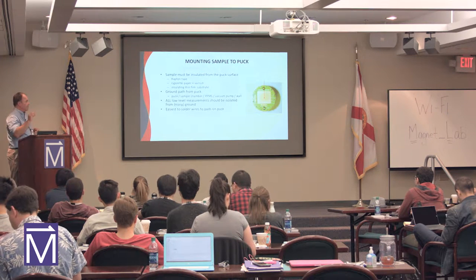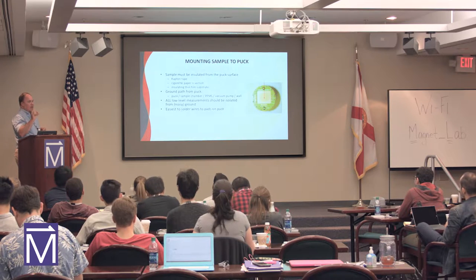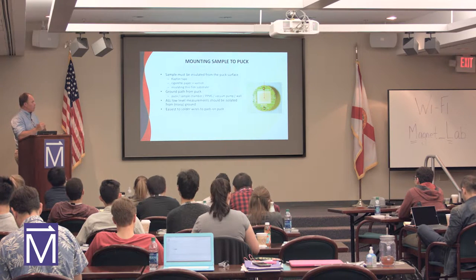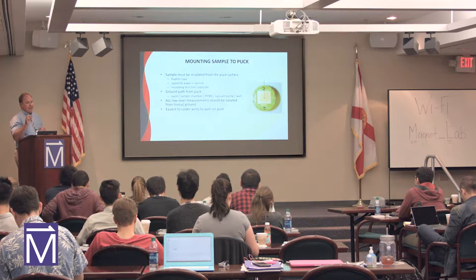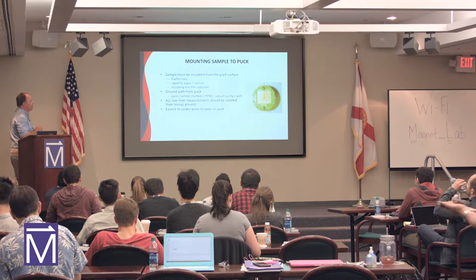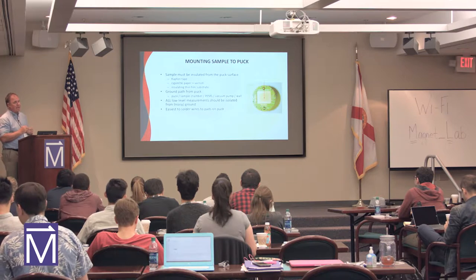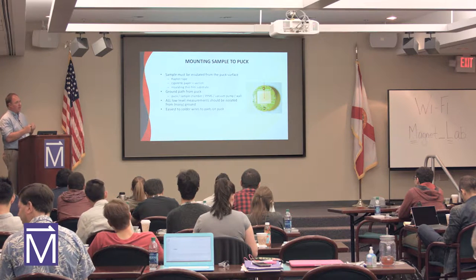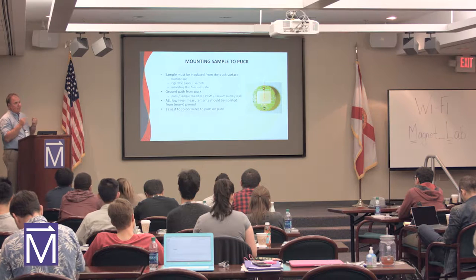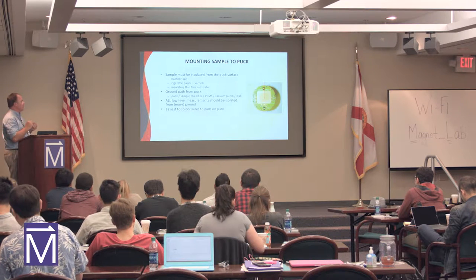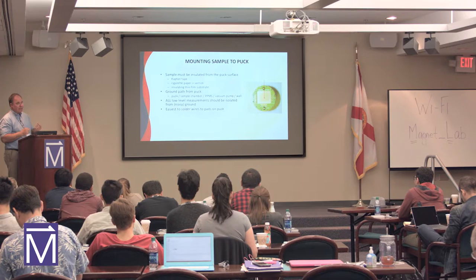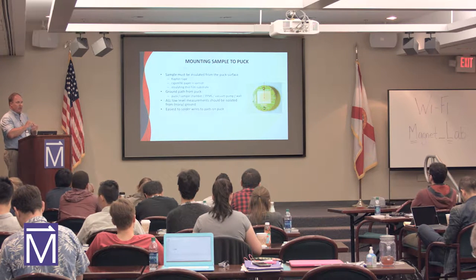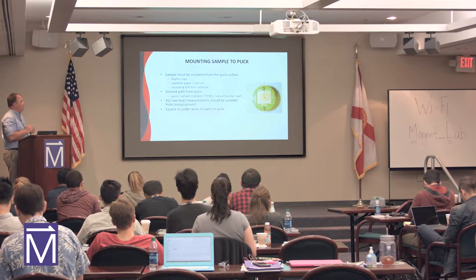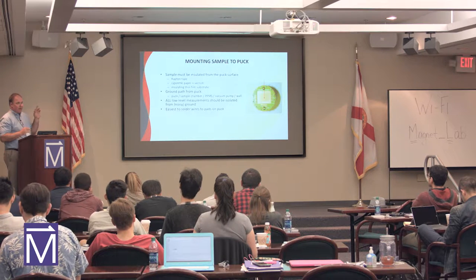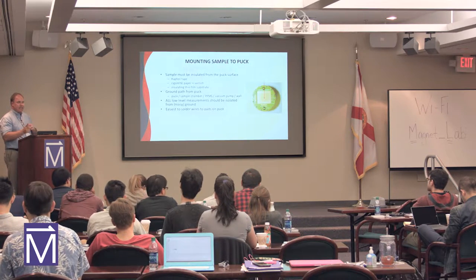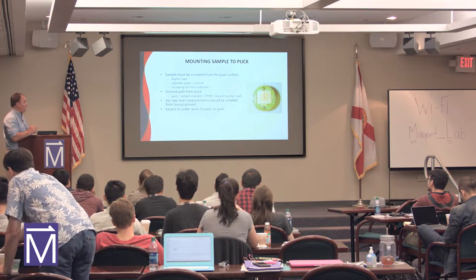And if you look closely at the pucks, you've got the printed circuit board where you can make your electrical contacts, and then you've got the backing plate. So you need to insulate your sample from the puck itself. So you can take a Kapton tape, cigarette paper with a little varnish on it, an insulating substrate, right? So you don't want to have your sample shorted to the puck itself. We'll talk about the ground path in a future slide about making ESD sensitive type measurements. So there's a ground path to that.